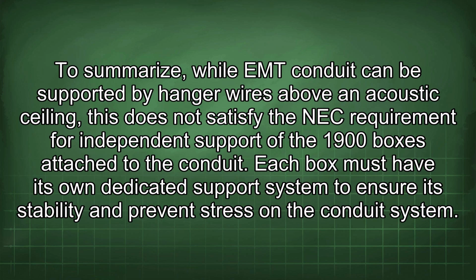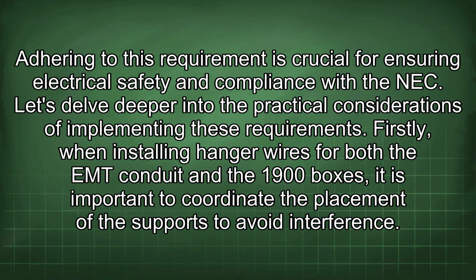To summarize, while EMT conduit can be supported by hanger wires above an acoustic ceiling, this does not satisfy the NEC requirement for independent support of the 1900 boxes attached to the conduit. Each box must have its own dedicated support system to ensure its stability and prevent stress on the conduit system. Adhering to this requirement is crucial for ensuring electrical safety and compliance with the NEC. Let's delve deeper into the practical considerations of implementing these requirements. Firstly, when installing hanger wires for both the EMT conduit and the 1900 boxes, it is important to coordinate the placement of the supports to avoid interference.